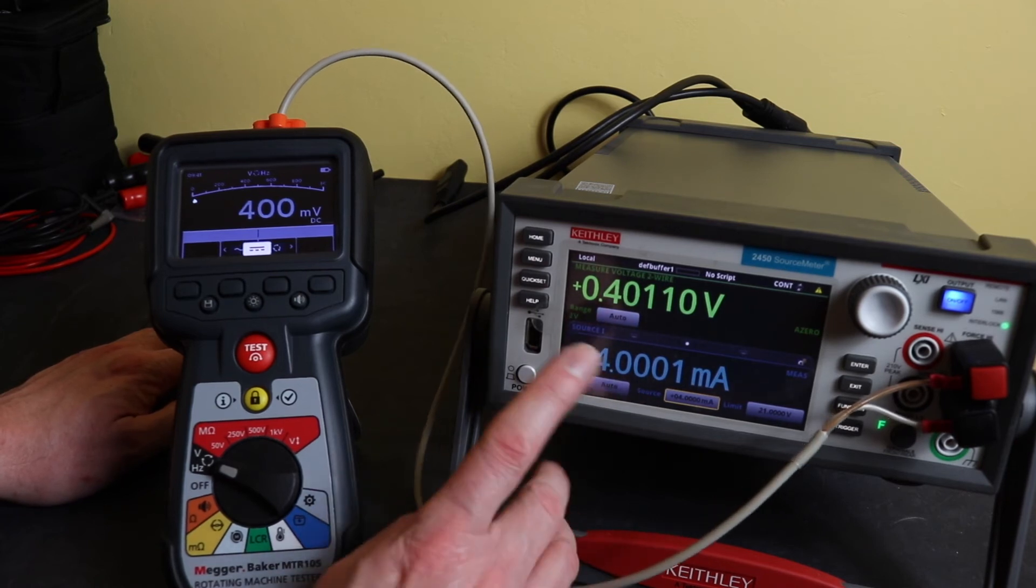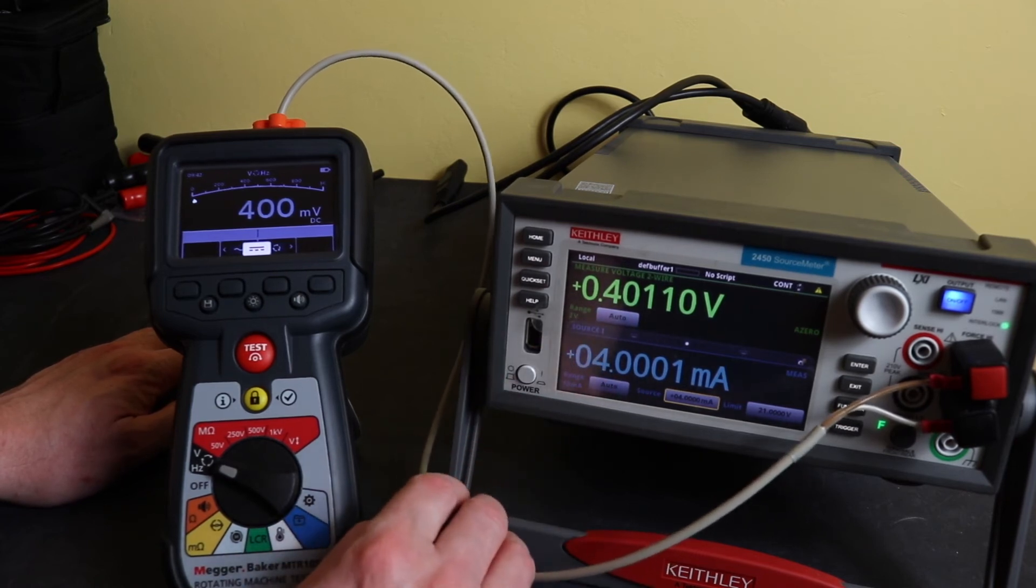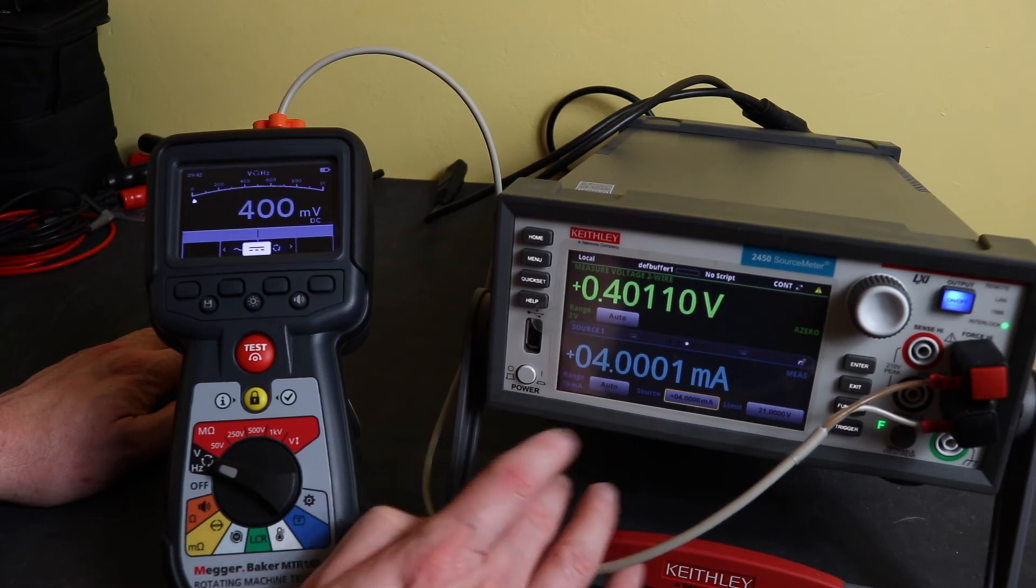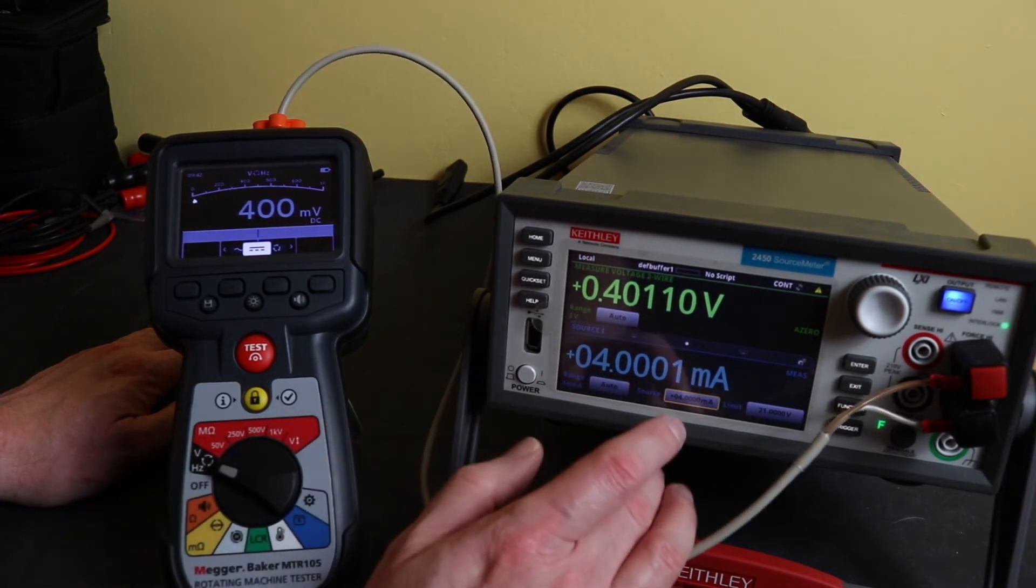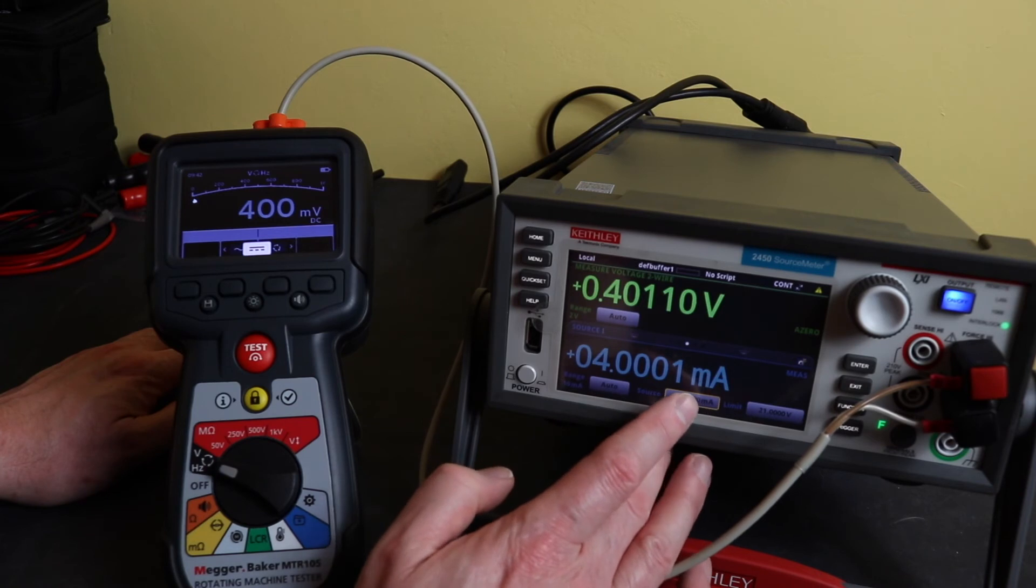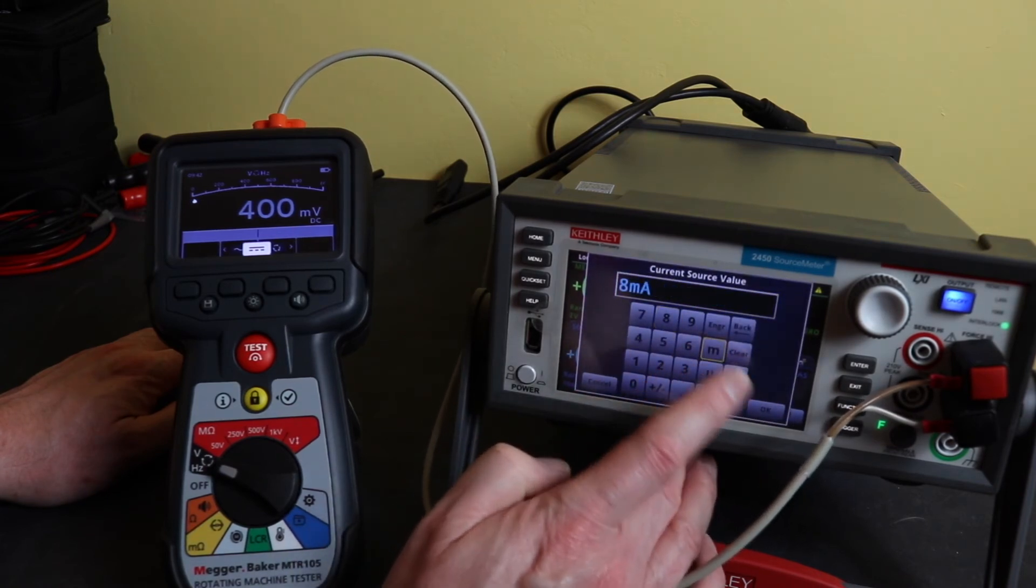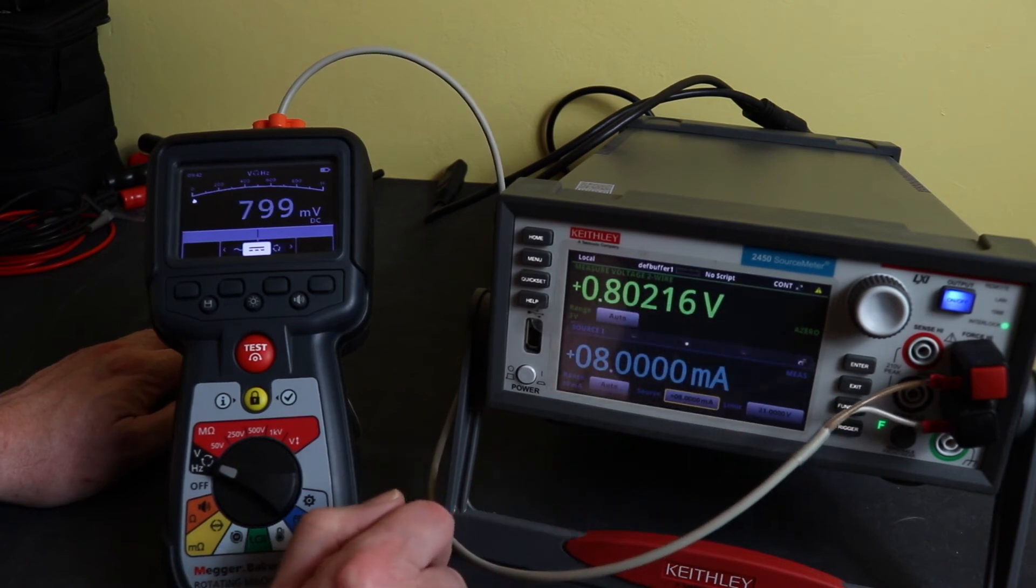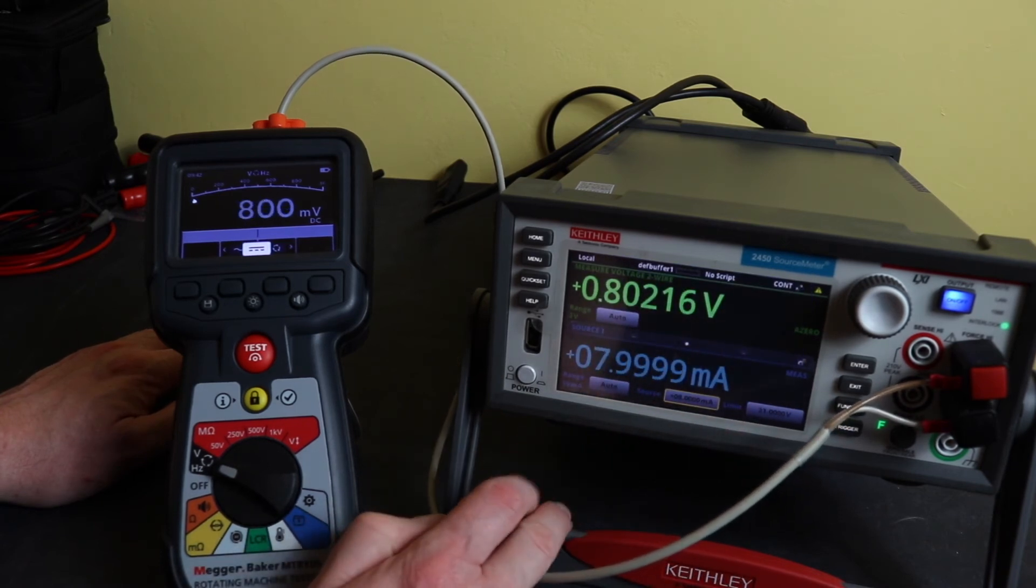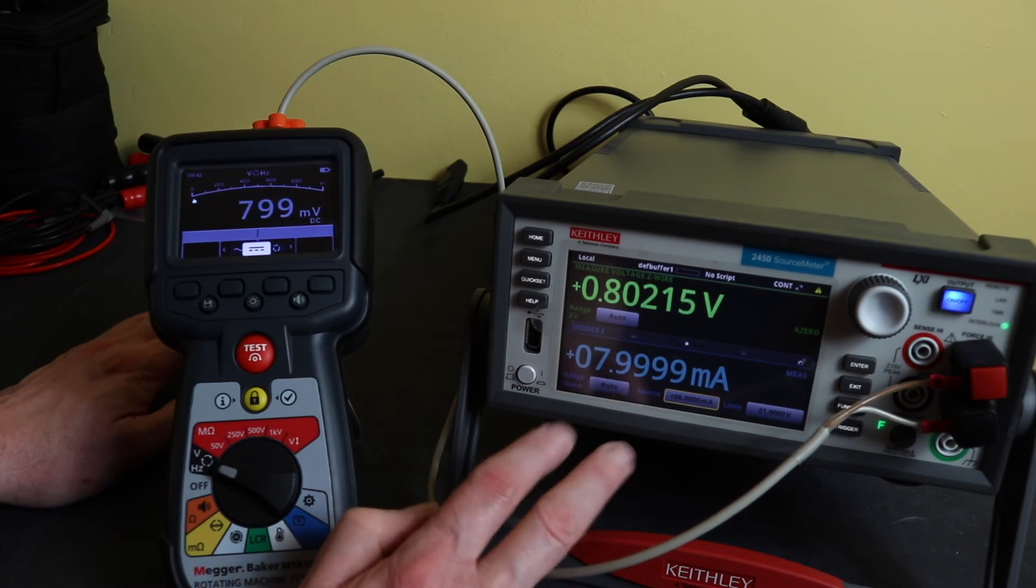And we're all setting it to four milliamps and there we see 400 millivolts so obviously with a 100 ohm resistor that's going to give me my four milliamps of current flow so I just divide it by 100 to get the current but you see the burden is now 0.4 volts so quite a bit higher burden when I'm using this test methodology and we'll go to eight milliamps.